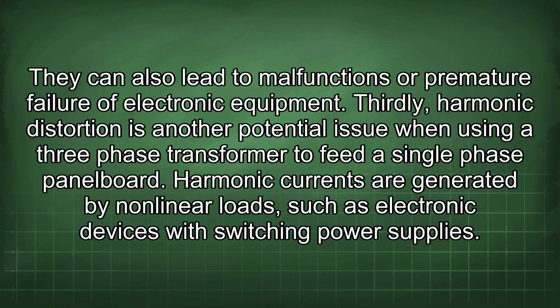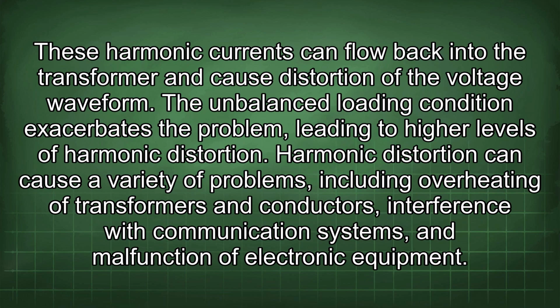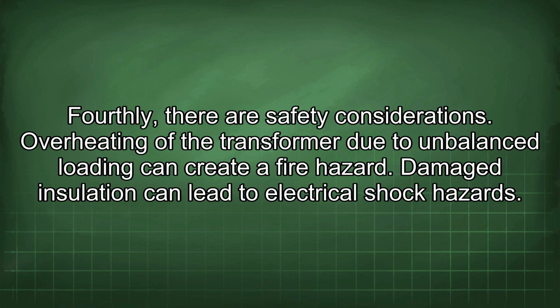Thirdly, harmonic distortion is another potential issue when using a 3-phase transformer to feed a single-phase panel board. Harmonic currents are generated by nonlinear loads, such as electronic devices with switching power supplies. These harmonic currents can flow back into the transformer and cause distortion of the voltage waveform. The unbalanced loading condition exacerbates the problem, leading to higher levels of harmonic distortion. Harmonic distortion can cause a variety of problems, including overheating of transformers and conductors, interference with communication systems, and malfunction of electronic equipment.